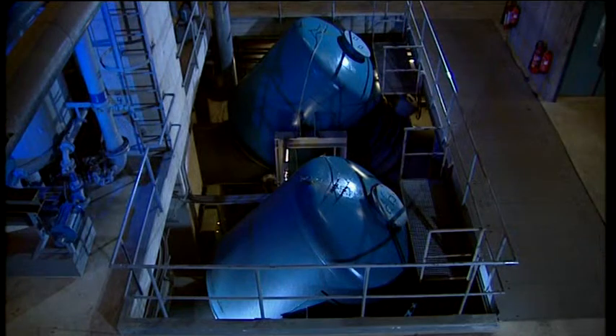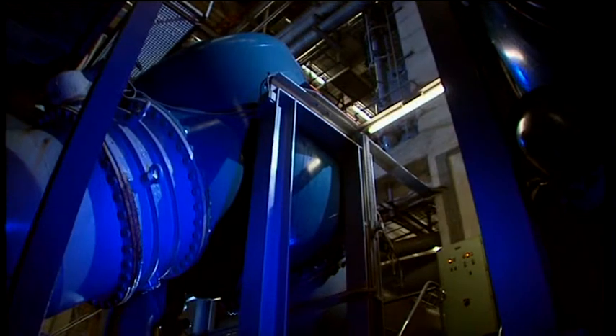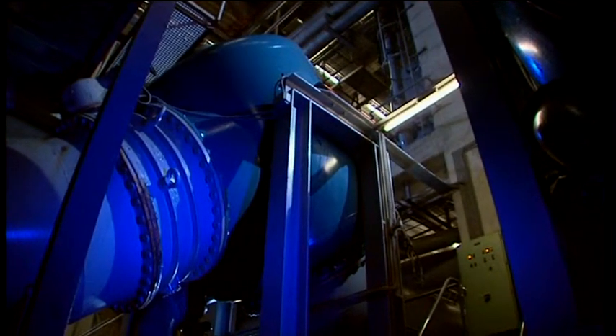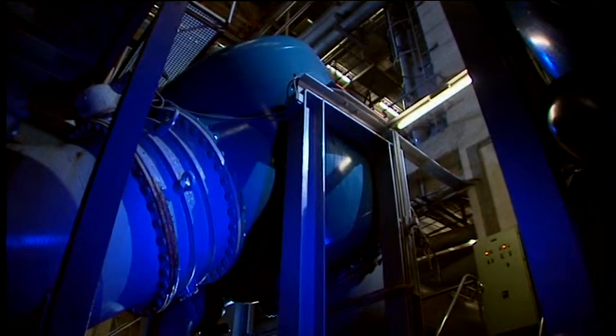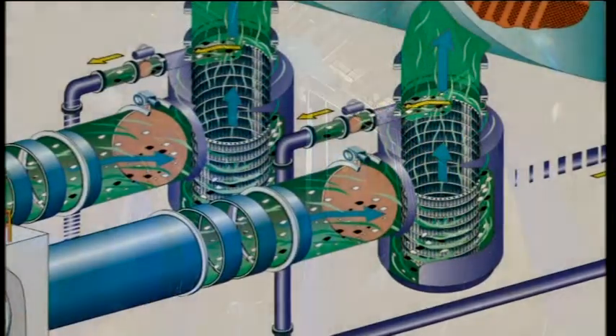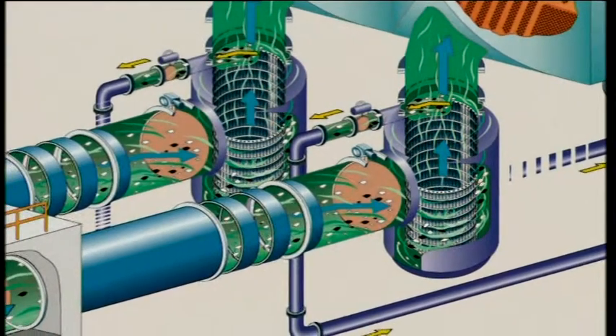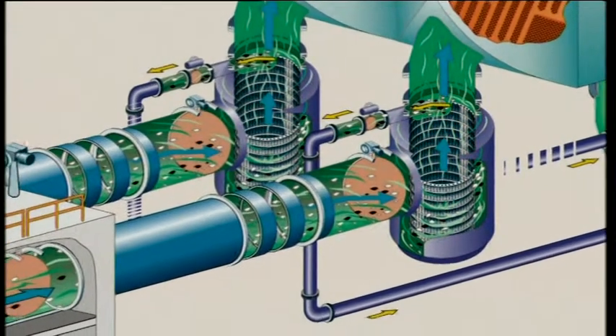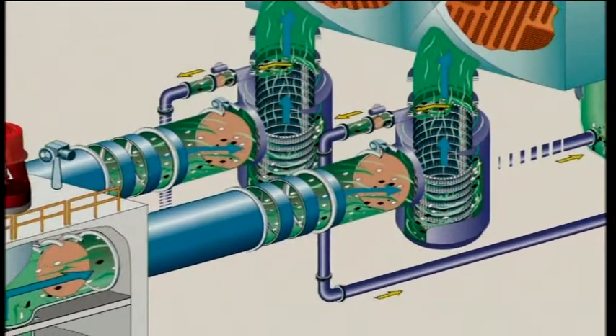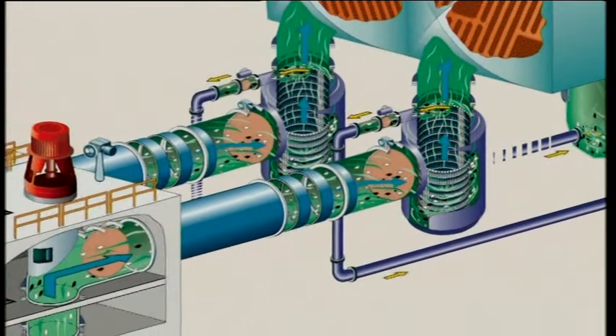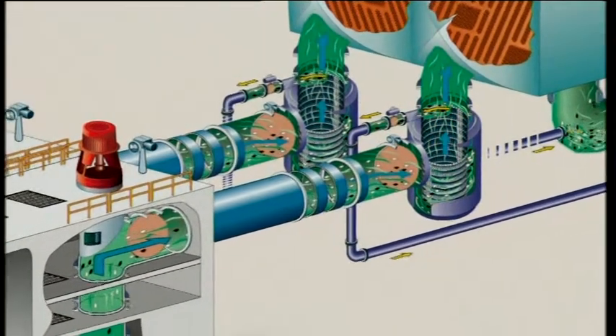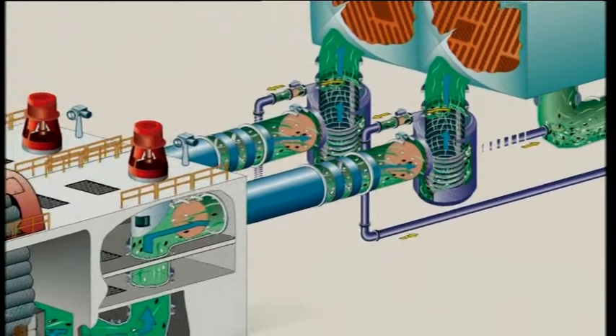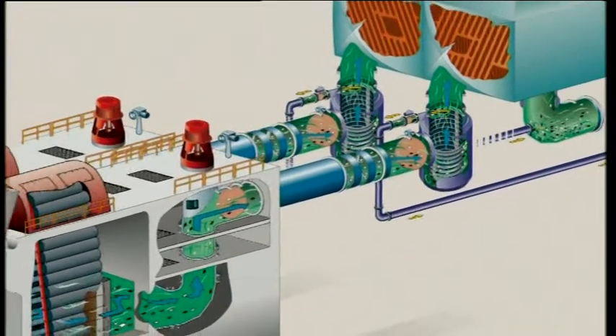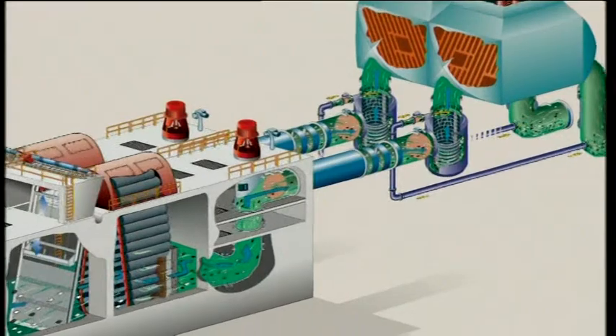Debris filters installed directly upstream of the condenser keep unpleasant pollution away from the heat exchanger tubes, thus guaranteeing free ball circulation. These debris filters, originally designed to filter out the mussels growing between the pumps and condenser, are supplementary elements to the pre-screening system. The ideal location of these mussel filters, deep inside the cooling water system, in other words, directly upstream of the object to be protected, caused Taprogge to reflect on the following.